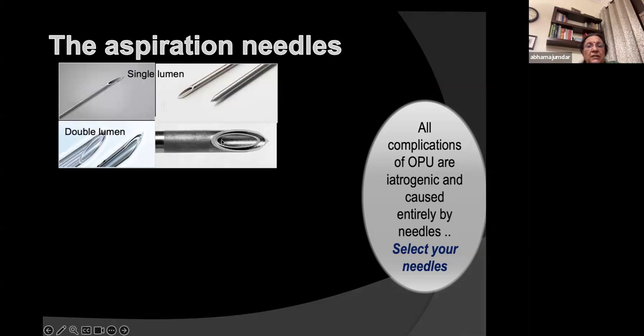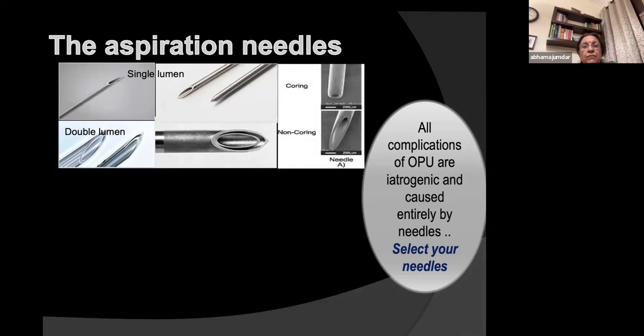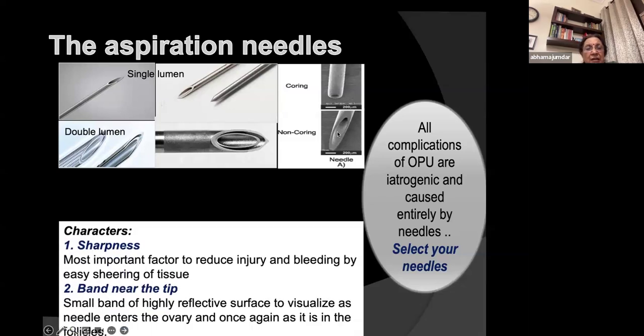These are coring needles. This is a double lumen one, and this is a single lumen, which has a core, and this is how the tip looks. So if it pierces, there's no tissue, it just pierces through the tissue till here, and then the other part enters. If it was round, then what would happen? It would go through the tissue, and that tissue could go into the needle. Now, this is a coring needle. The whole tip is like this. It may be very thin, but it could catch tissue into it. Whereas in this, there is very little possibility of it being blocked by tissue entering the needle.